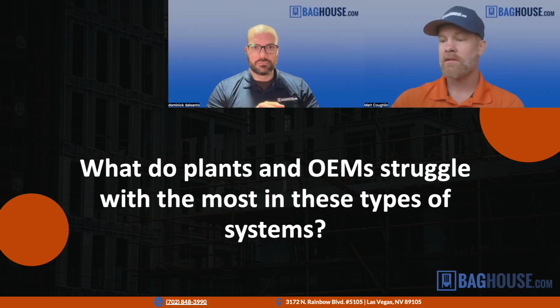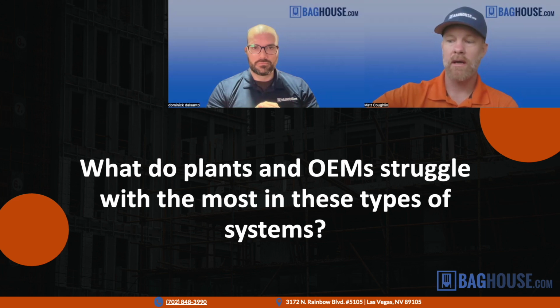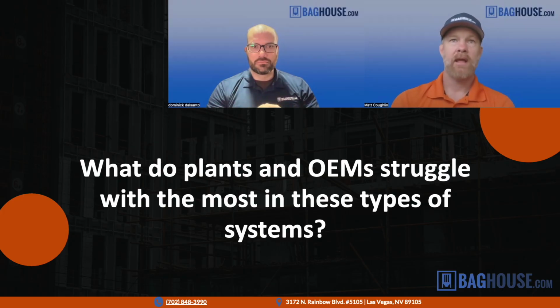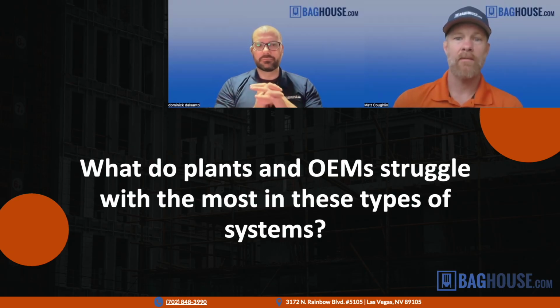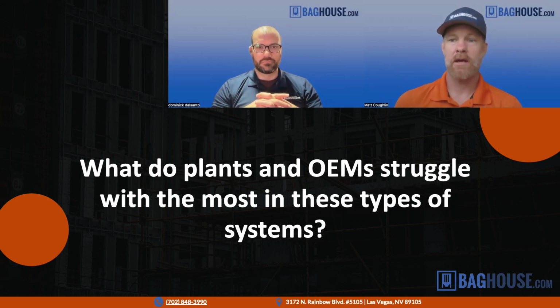And then over time, these types of facilities have a way of changing. Processes get moved around, pickup points get added, often for good reason, because you have a new machine over here and you need to reroute this ductwork over there. We'll go into facilities where the dust collection system may have been perfectly designed to start with, but things have changed. Ducts have been added, pickup points added, moved, or closed off. Then you have balancing issues in the ductwork. You've added pickup points and watered down the airflow at each pickup point where you need it, and people are left scratching their heads as to why it's so dusty in the facility.